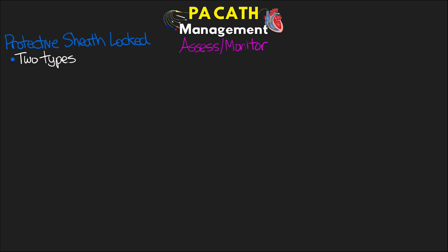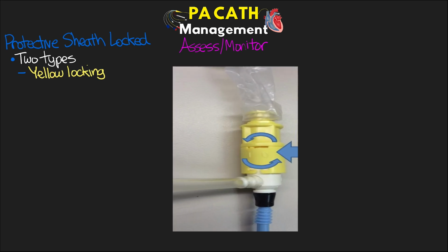All right, and so lastly, I did want to mention a few things to keep in mind for our ongoing monitoring and assessment. So first off, you want to quickly check and make sure that the protective sheath is locked. So there's primarily two types of protective sheaths that you'll see with two different types of locking mechanisms. First, and this is actually preferably my favorite, is the yellow locking position. So this one here twists on and locks into the sheath itself, which you can see an example of that here. And then from there, there's actually a twisting motion to lock the protective sheath in place. You can see it here from this picture where there's both an I and an O. So the I is going to be our locked position, and then the O is going to be our open or unlocked position.